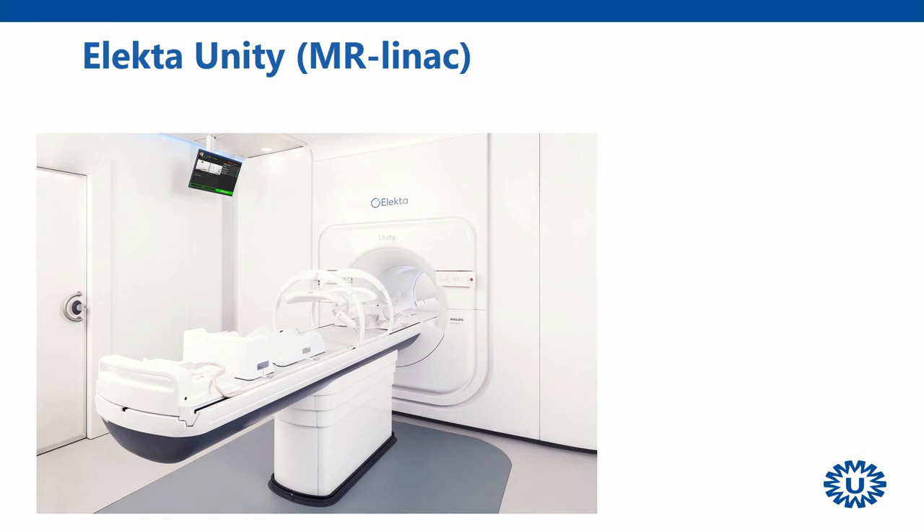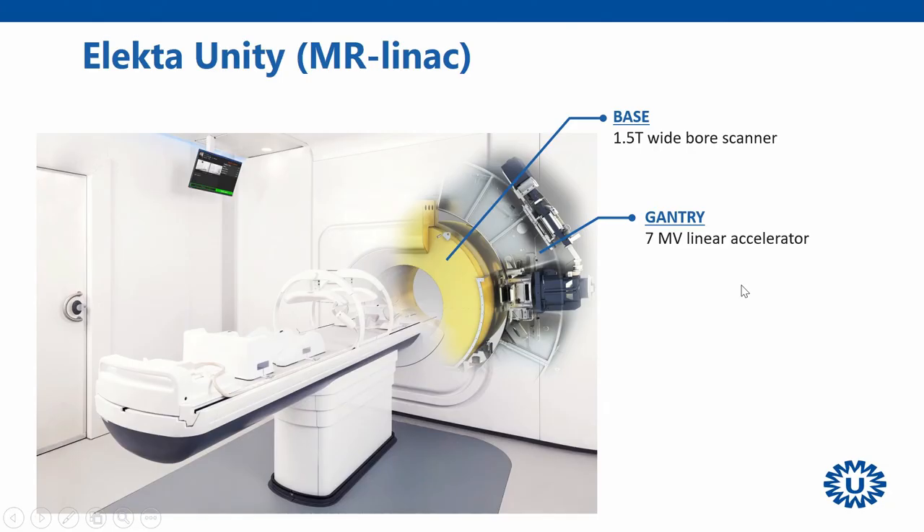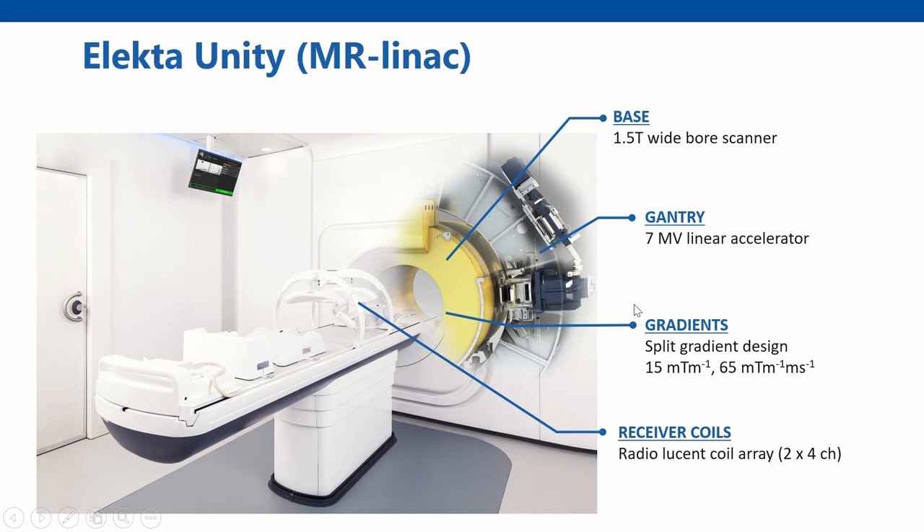The MR-Linac system is based on a 1.5T MRI scanner, based on the Ingenia Philips platform. But as you take away the covers, you see that behind them there's a large ring-shaped gantry which houses a 7 MV linear accelerator pointing towards the isocentre of the system. In order to allow a radiation window with relatively little attenuation, we have a split-gradient design with corresponding specifications, and the coils used are especially dedicated to this system as they must also be radio-transparent.